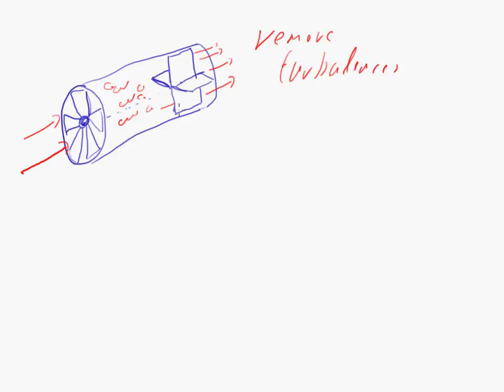The advantage is that those guide vanes, when they remove those turbulences, they convert those turbulences into static pressure. That means that fan would produce more static pressure with those guide vanes than without. And thus, that raises also the fan's efficiency.